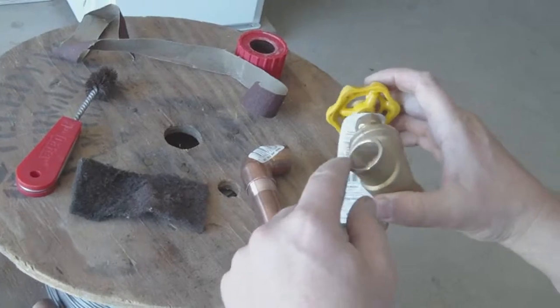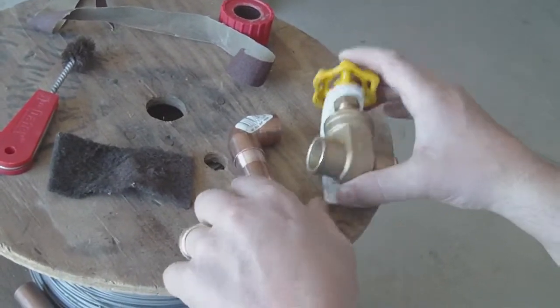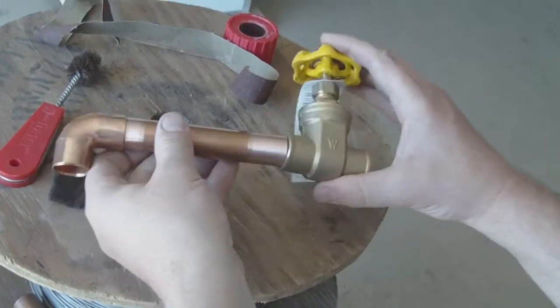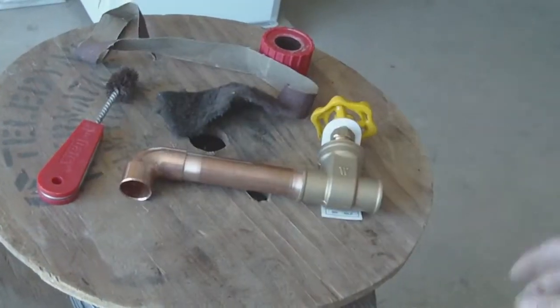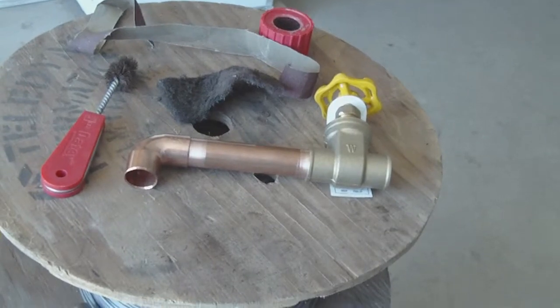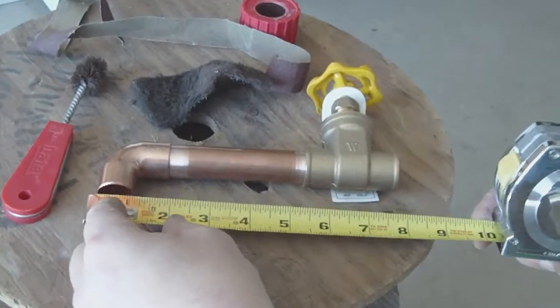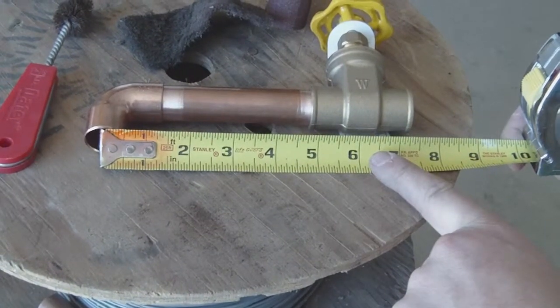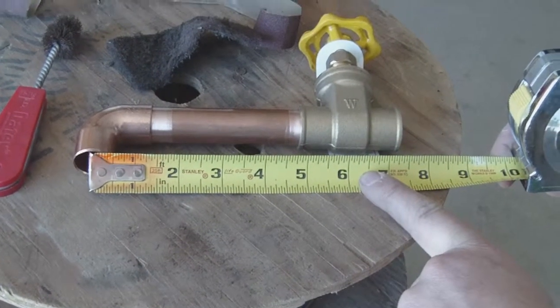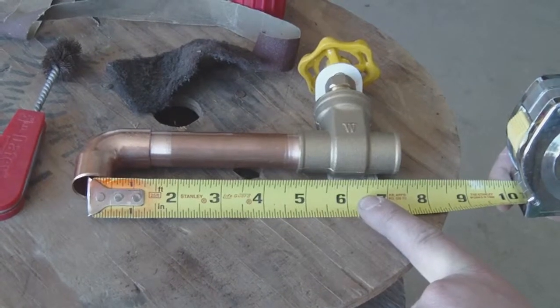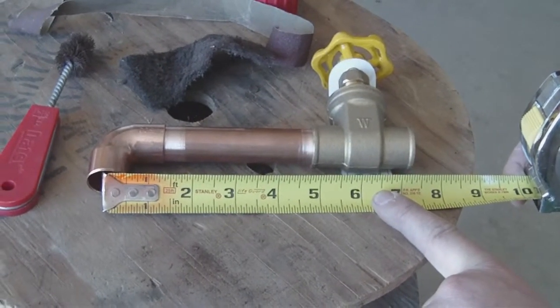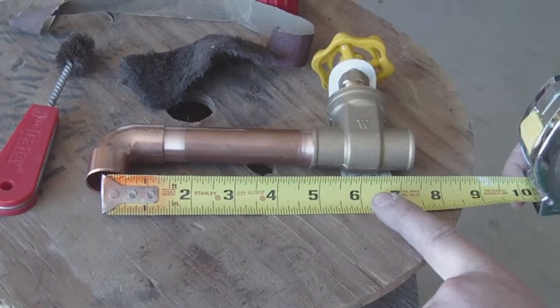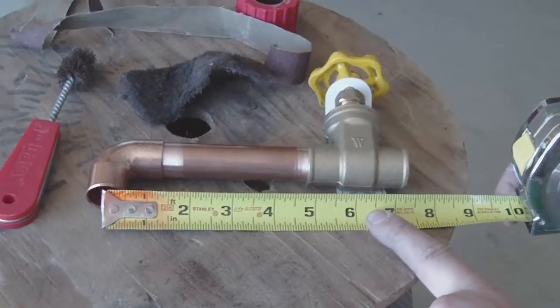I clean this up, look at the difference here, how shiny that is, that's brightly polished. This is brightly polished, brightly polished. They're in. I do my final rough-in measurements, I grab my tape measure to make sure that everything is still what I want it to be, which we were saying was six inches, and it is. So it's right on six inches. Everything is fine. I always want to measure, measure, measure, measure. Because once I sweat solder it, it's a pain to undo it. So this is a one and done function. And that ends this section of getting it prepped and ready to go.